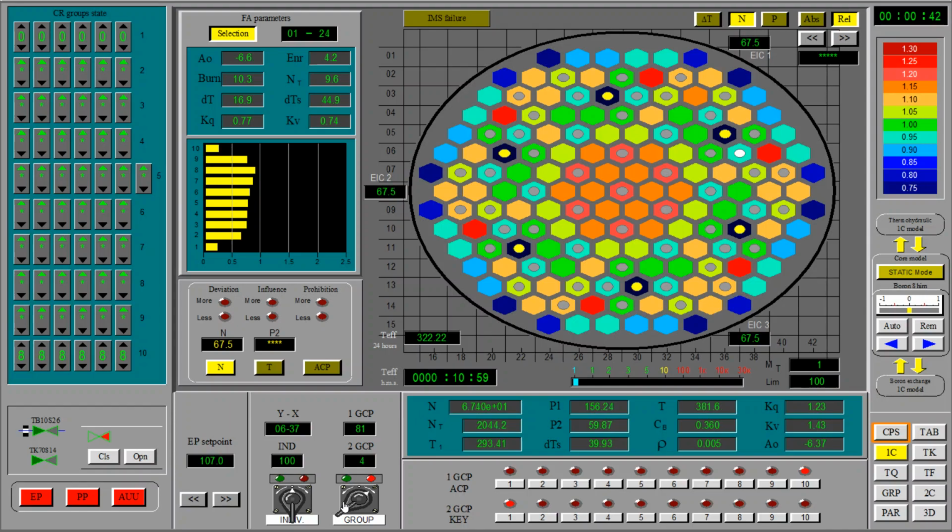The thing here is, if during these 10 minutes not a lot of Xenon poison was created, we will be able to go up to 100% of nominal power just withdrawing group 1, which was the one that was inserted to reduce the power of the reactor.